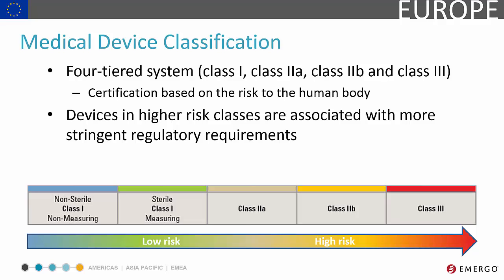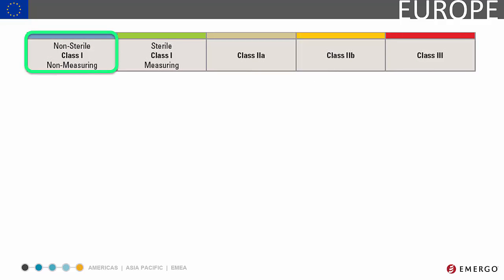The higher the classification, the more stringent the regulatory requirements. Unlike other regions, Europe does not use existing devices as a basis for classification. Class 1 devices represent the lowest level of risk as they're not complicated to operate, nor do they pose great risk to patients. All non-invasive devices are Class 1, unless otherwise stated in the Medical Device Directive.